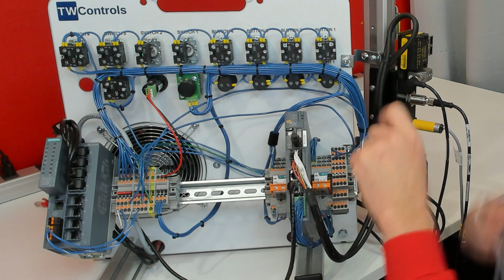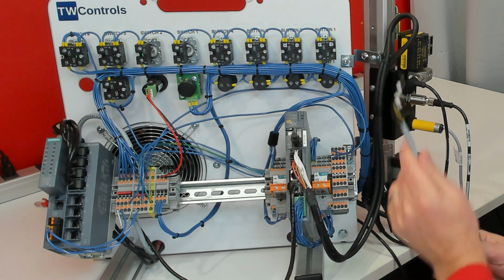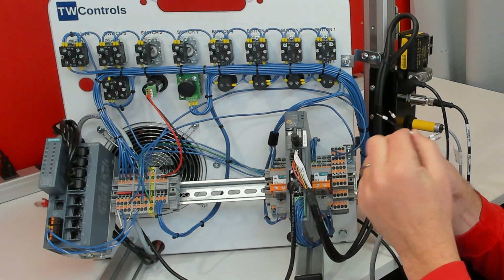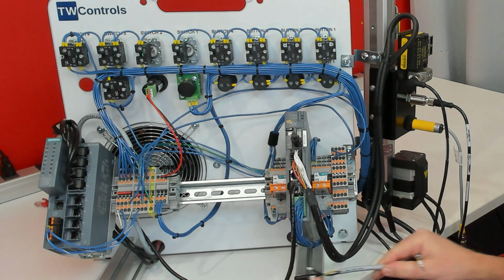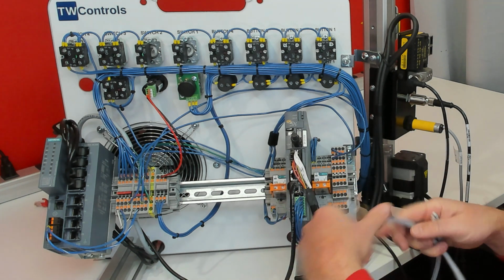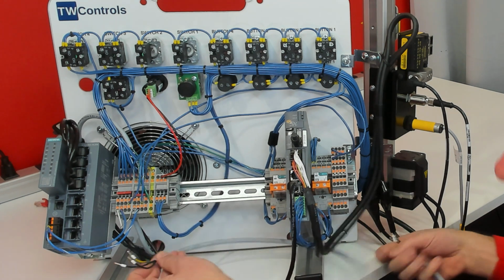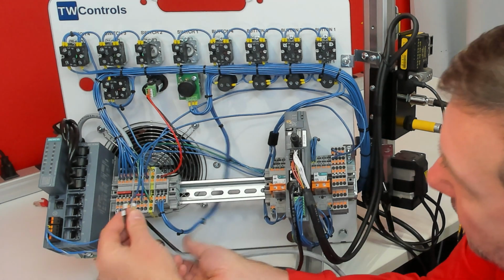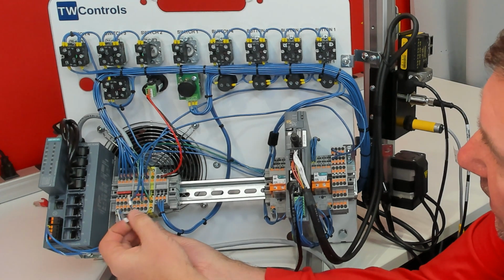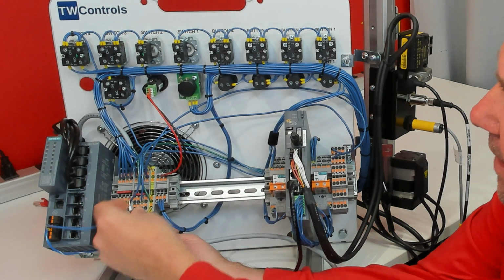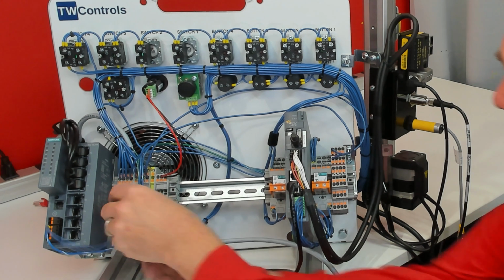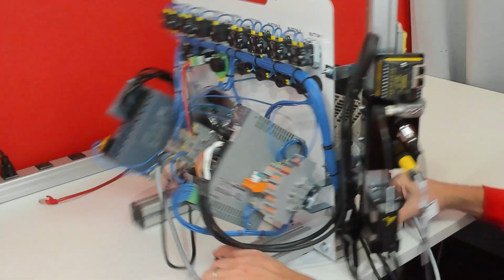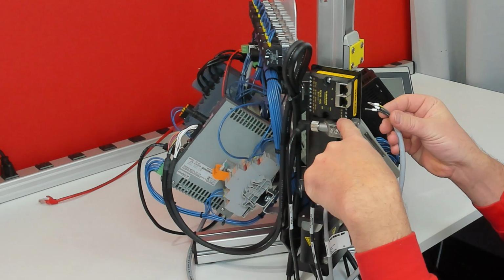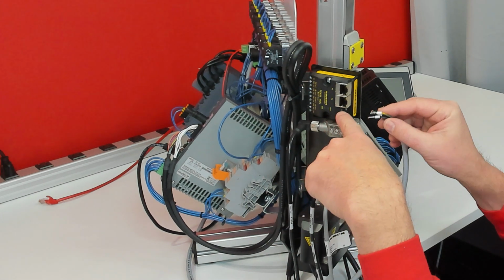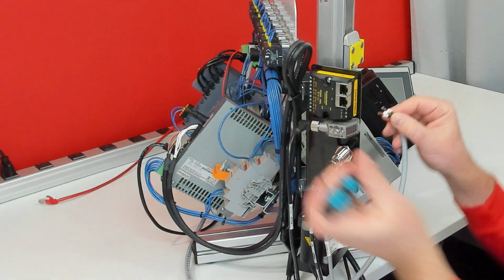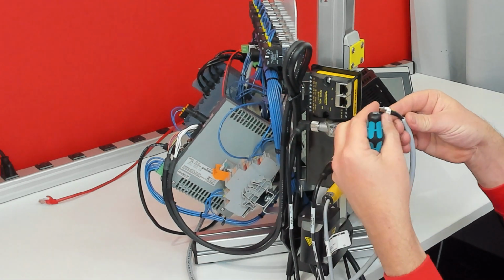We'll go ahead and power up our IO link. And we're going to do that with this cable here. It's got a green wire and a one and a two. We're going to take one, our plus 24 volt, and two, our minus 24 volt. So I'm going to scoot this through here. Then we're going to plug the green into the ground terminal, and two will go into our minus. And one will go into our plus. And now we'll run this over to our IO link. And they are from the bottom, plus, minus, and our ground. So we're going to put one, two, and then ground.